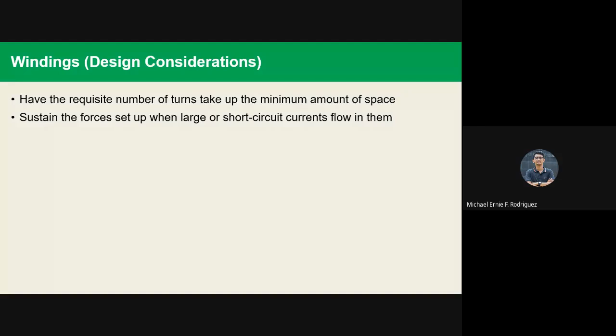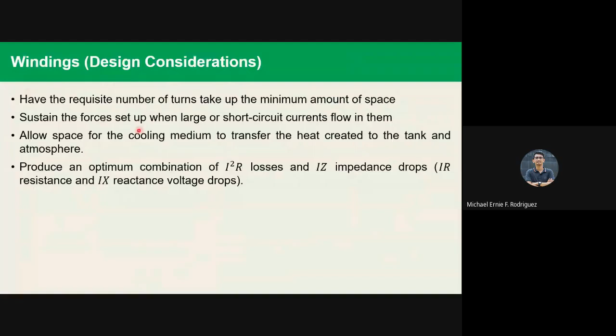The next consideration is to sustain the forces set up when large or short circuit currents flow in them. And then allow space for the cooling medium to transfer the heat created to the tank and atmosphere. Last, it should produce an optimum combination of I squared R losses and IZ impedance drops, that is IR resistance and IX reactance voltage drops. So these are the different design considerations for your windings, meron tayong apat.